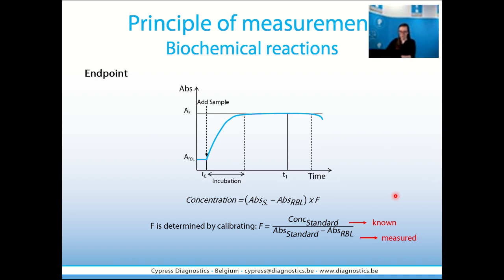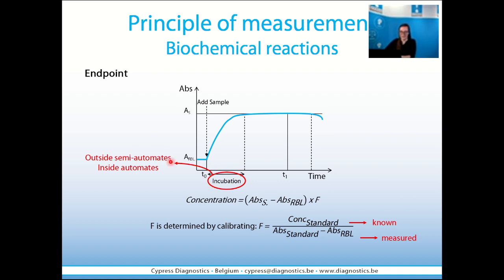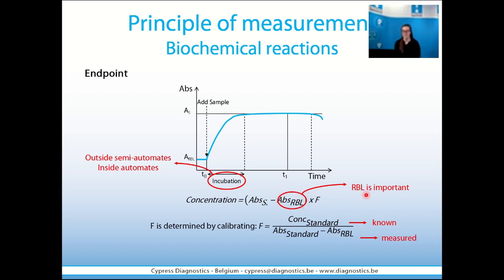What is important to know? The incubation happens outside of semi-automates and inside automates. You will always have to measure a reagent blank for endpoint reactions because this parameter is included in the calculation. If the reagent blank is not calculated, your concentration of analyte will not be correct.